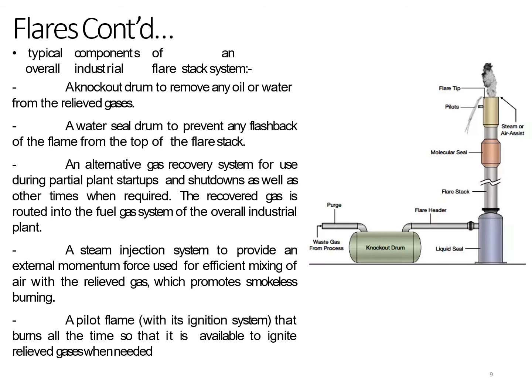An alternative gas recovery system for use during partial plant startups and shutdowns as well as other times when required. The recovered gas is routed into the fuel gas system of the overall industrial plant. A steam injection system to provide an external momentum force used for efficient mixing of air with the relieved gas, which promotes smokeless burning. A pilot flame with its ignition system that burns all the time so that it is available to ignite relieved gases whenever needed.